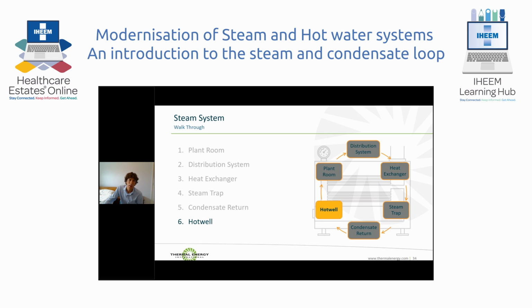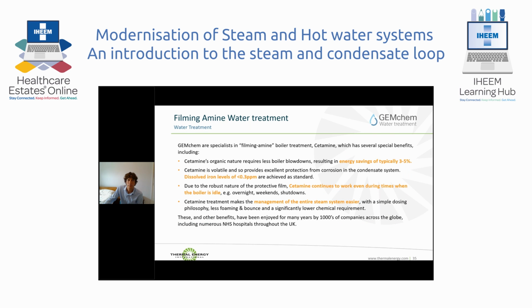We then return finally to the hot well or deaerator. This is where the hot water is returned and stored for use in the boiler. As I said earlier in our presentation, boilers operate as giant kettles concentrating salts. Water treatment is essential to maintain the safe operation of boiler plants. This is traditionally done through the adding of phosphates as a sludge conditioner to prevent scale formation. Effectively, they just create a different type of scale that doesn't adhere to the tubes, that falls off and drops to the bottom of the boiler, and sulphites to act as an oxygen scavenger and prevent corrosion. Both of these chemicals add to the total TDS, the total dissolved solids within the boiler, increasing the amount of blowdown required. An alternative is a filming amine treatment, such as supplied by GemChem.